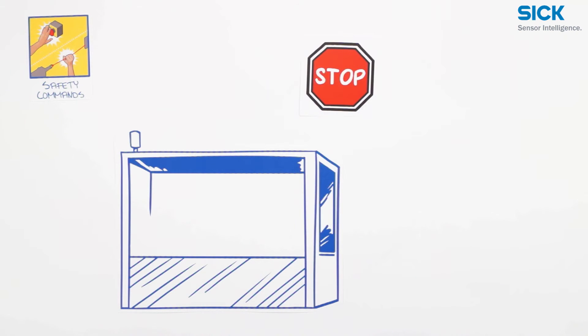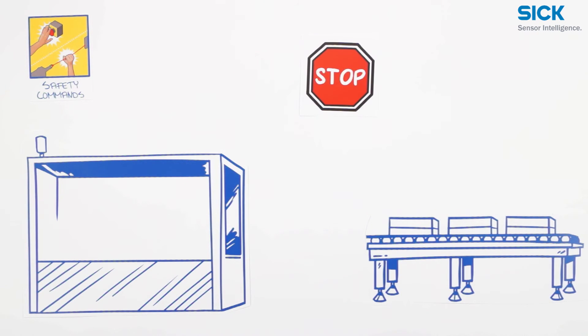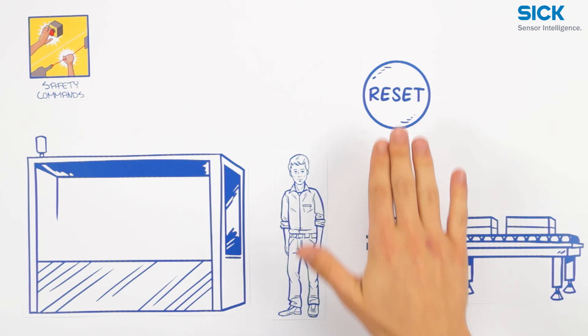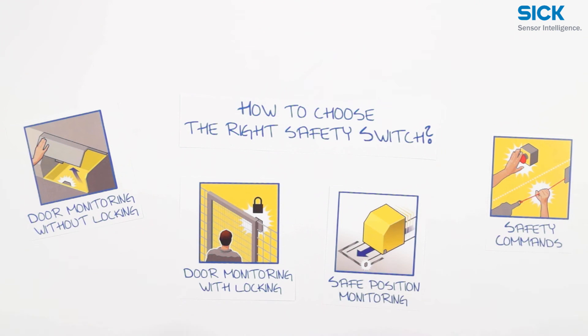Finally, let's look at safety commands. To stop a machine or system immediately in case of an emergency, emergency stop push buttons are the right choice. For long distances you should use rope pull switches. In some cases, after initiating a stop function, people might still remain in the hazardous area without being detected — in this case the protective device must be reset using the reset push button before restarting the machine. For setup mode, you could use an enabling safety switch. As you can see, the SICK portfolio of safety switches can solve many different applications, including yours.